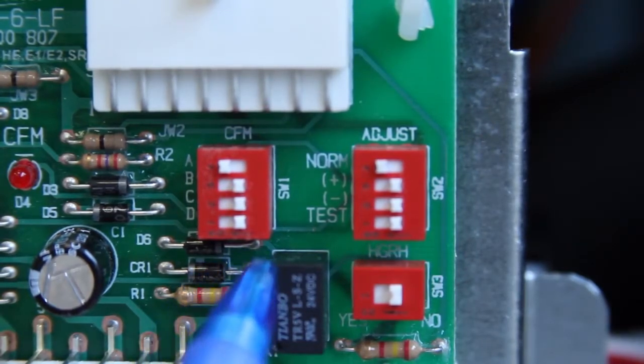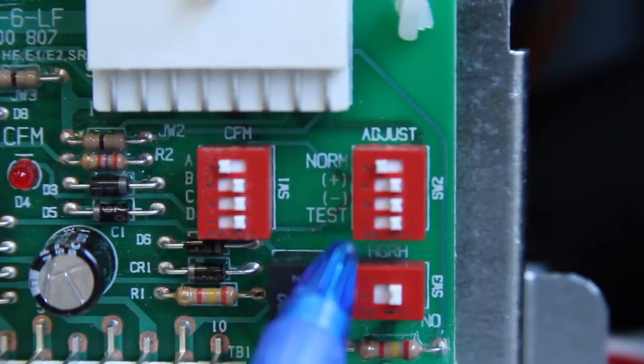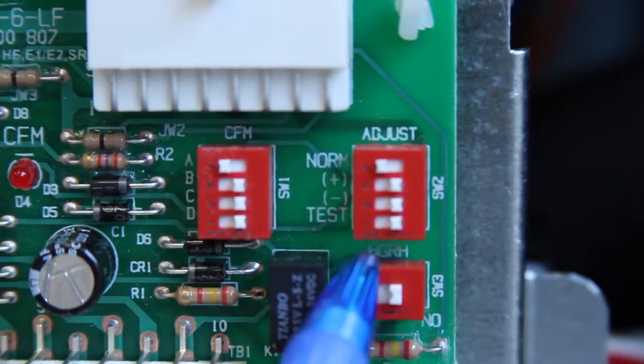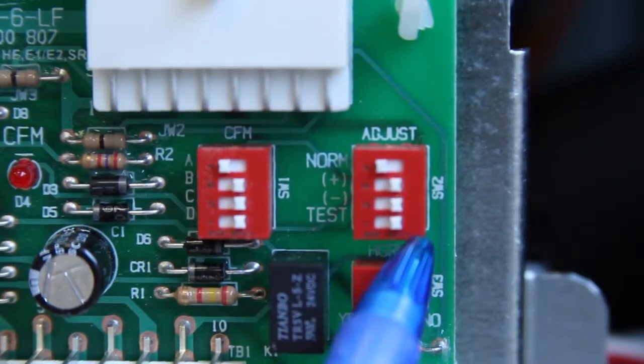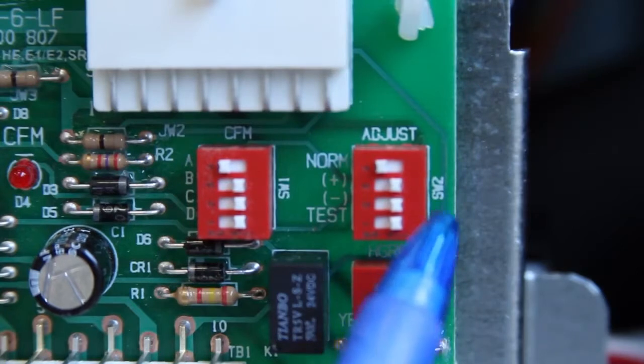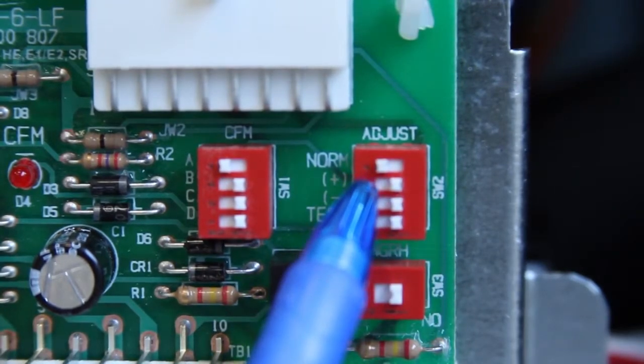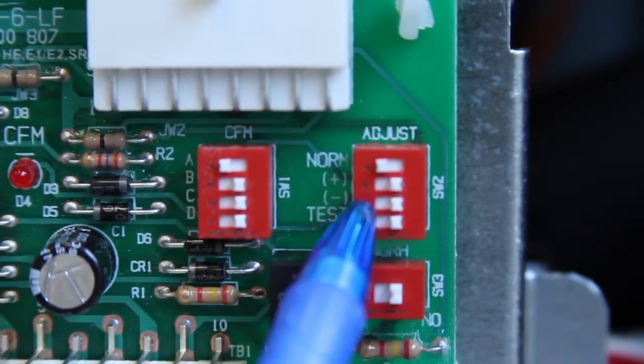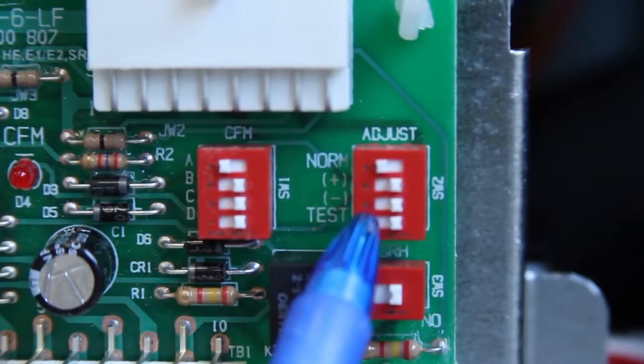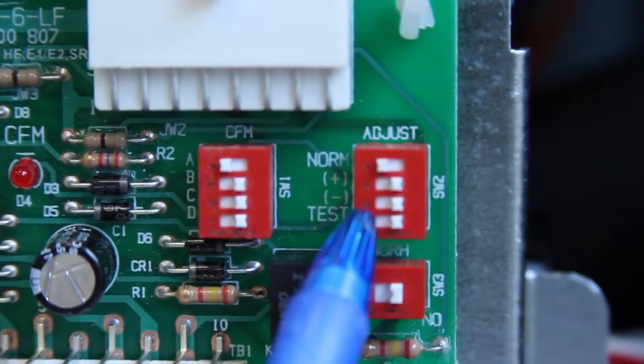Over to the right of that set of dip switches are 4 more dip switches labeled adjust. Here again, the left position is on, the right position is off. From the factory, the top switch labeled norm or normal is in the on position, which means you will get your nominal CFM listed in the blower tables on page 59. If you put the plus switch in the on position, that will increase the CFM by 15%. If you put the minus dip switch in the on position, you'll get 15% less CFM.